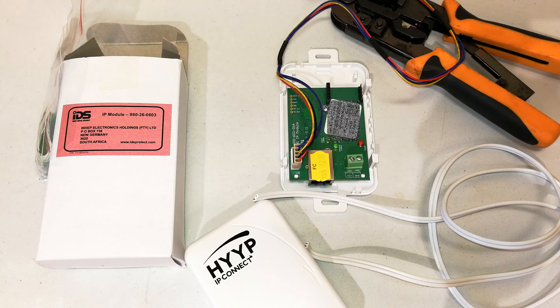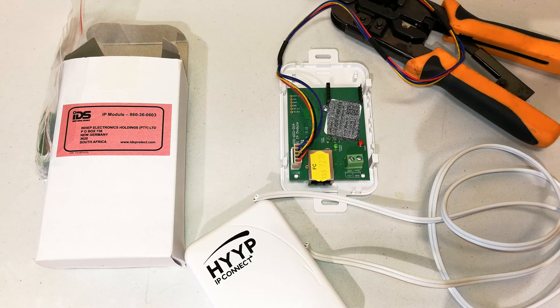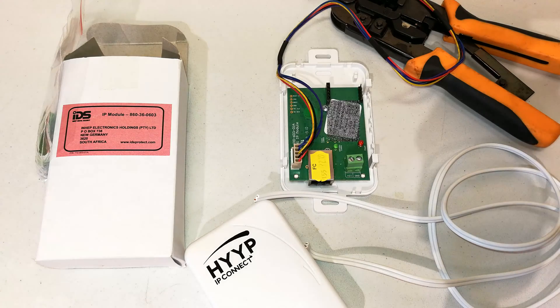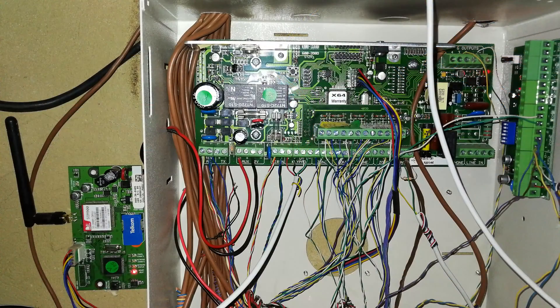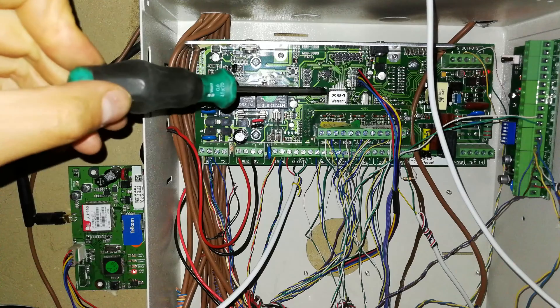I just want to show you inside. If I open this up, you will see there is a terminal there and that terminal is for power supply. It says 12 volts, so you will need just a two-core cable to connect from there 12 volts to your alarm panel. You could also use comms cable.